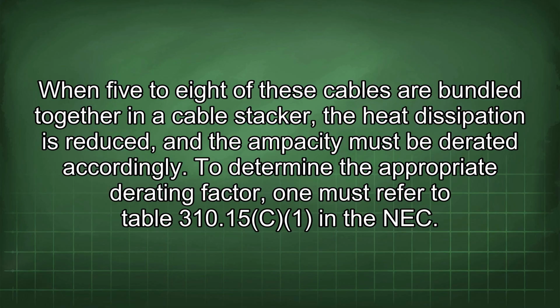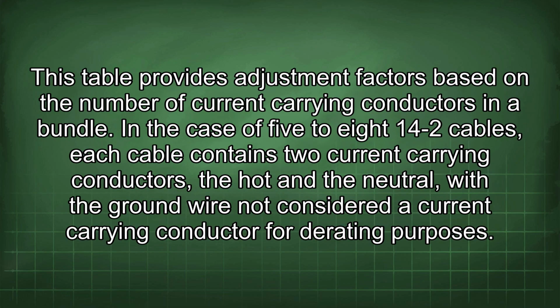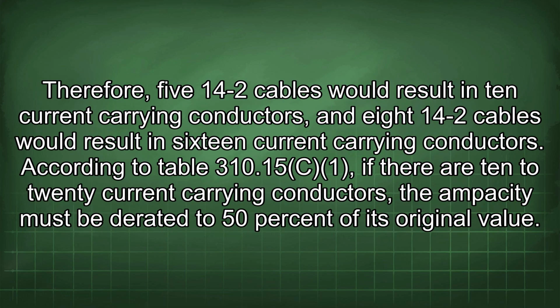To determine the appropriate derating factor, one must refer to Table 310.15 in the NEC. This table provides adjustment factors based on the number of current-carrying conductors in a bundle. In the case of 5 to 8 14-2 cables, each cable contains 2 current-carrying conductors, the hot and the neutral, with the ground wire not considered a current-carrying conductor for derating purposes. Therefore, 5 14-2 cables would result in 10 current-carrying conductors, and 8 14-2 cables would result in 16 current-carrying conductors.